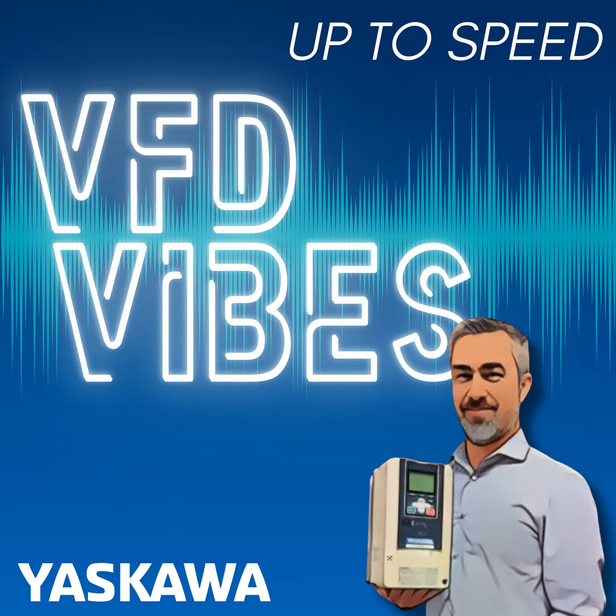Now, it's important to know that that input phase loss fault can also be generated from an output condition, and we'll touch on that now so you understand how the drive works and detects the circuit. Let's say you have a cooling tower up on a roof, and it's old, it's been up there 20 years, and it always had some vibration, and now finally one of the fan blades has fractured or fallen off, it's sitting in the basin, and this is now up there. It's completely unbalanced and it's really womping away as it's accelerating.